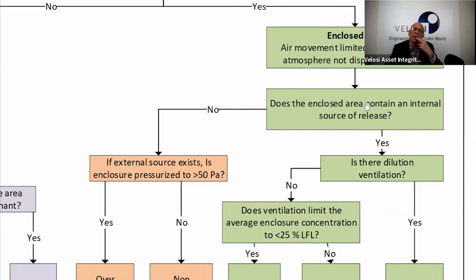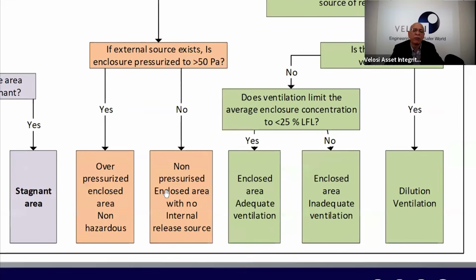If you have an enclosed area, let's say a control room near the facility, or a substation. A substation does have stored oil in the transformer and switchgear. But if we take a control room, normally hydrocarbon is not available inside, so it will not have any internal source of release. In that scenario, we try to make that building a positively pressurized building, so that in case hydrocarbons are released outside, they are unable to penetrate into the building. So for those buildings we need to maintain positive pressure.